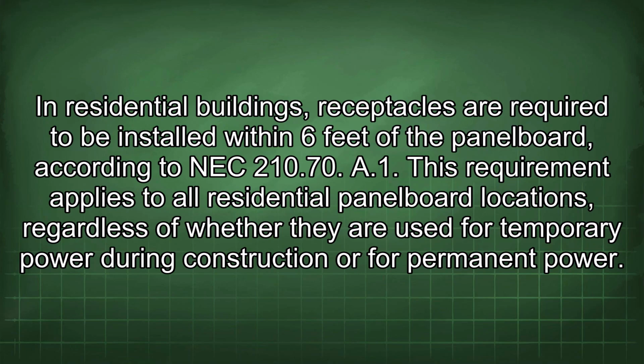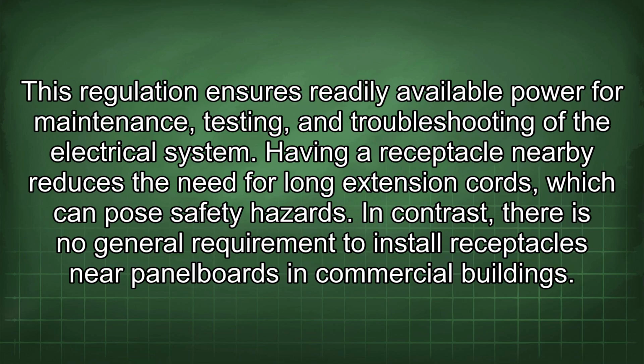In residential buildings, receptacles are required to be installed within 6 feet of the panel board, according to NEC 210.70. This requirement applies to all residential panelboard locations, regardless of whether they are used for temporary power during construction or for permanent power. This regulation ensures readily available power for maintenance, testing, and troubleshooting of the electrical system. Having a receptacle nearby reduces the need for long extension cords, which can pose safety hazards.